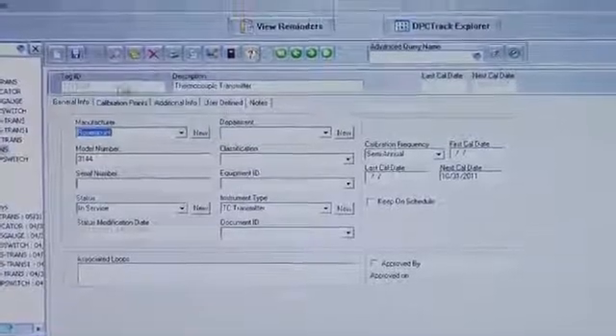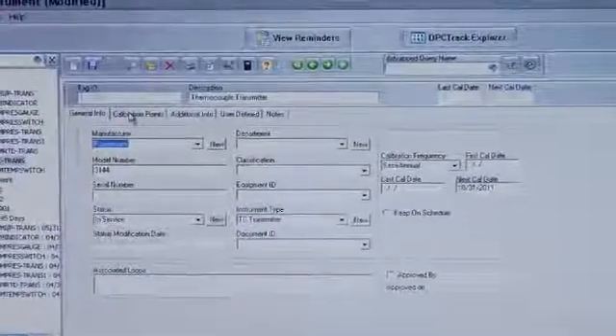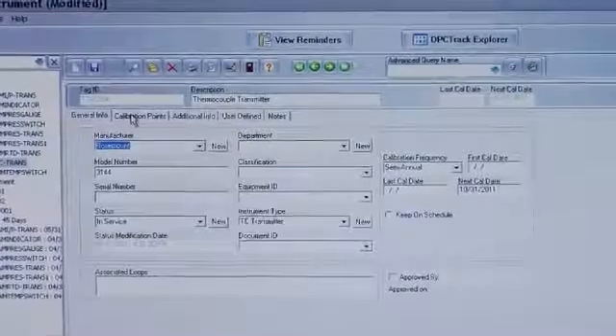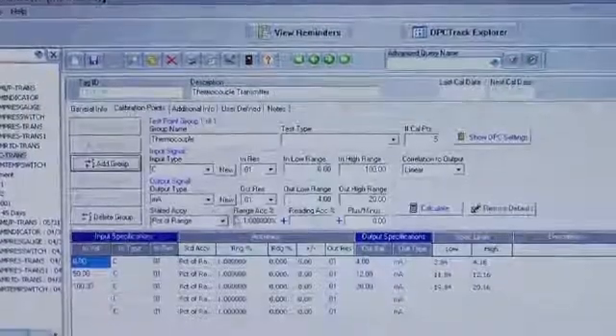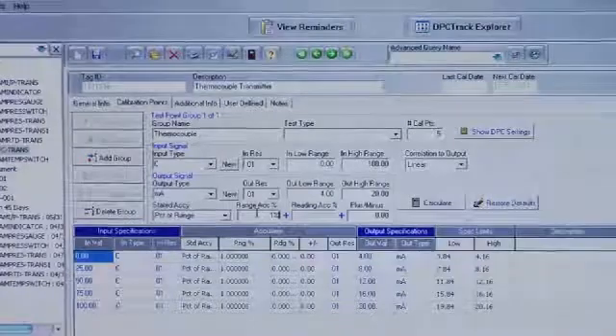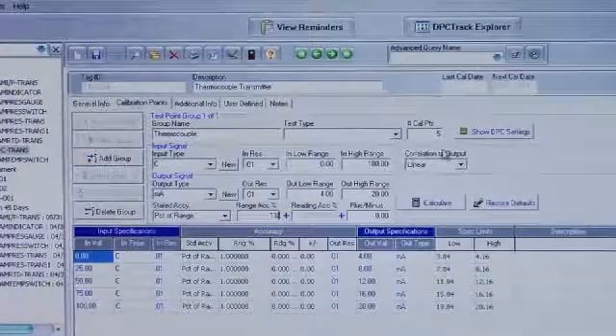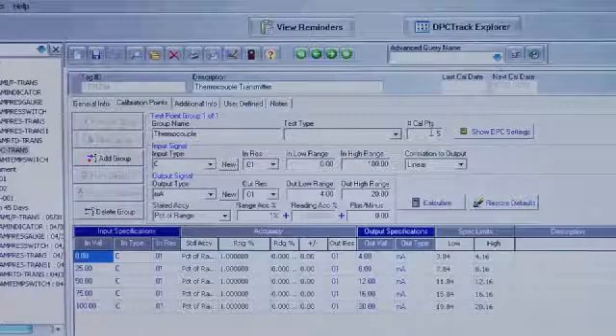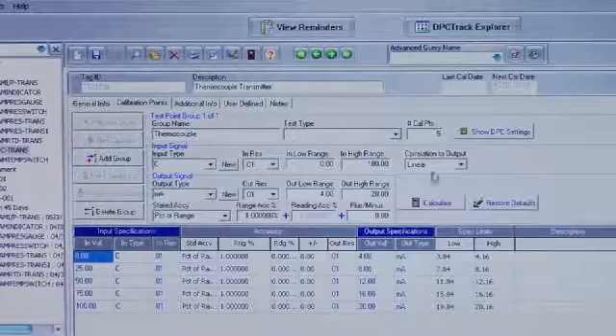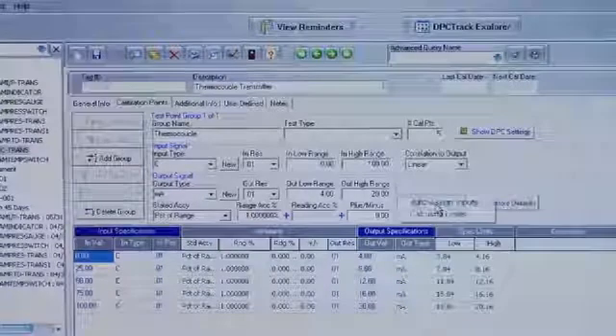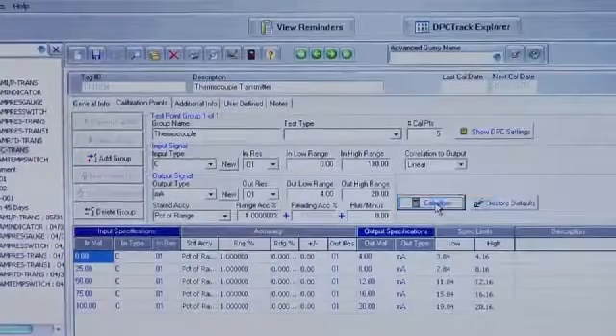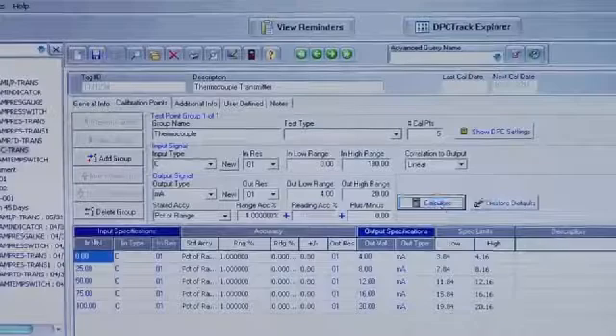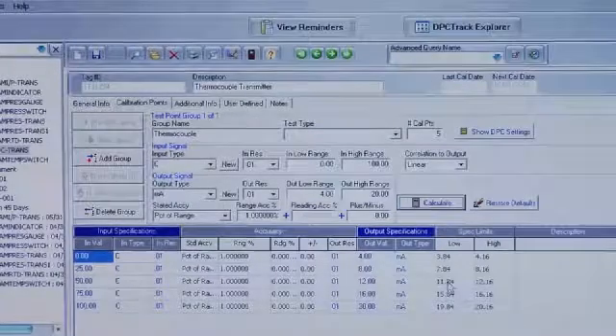Let's modify this tag to match the tag that we are going to calibrate. Select calibration points, input the test tolerance, and input the number of test points that you want to test. Select calculate and auto-design limits, and it will automatically calculate the test points for this tag.